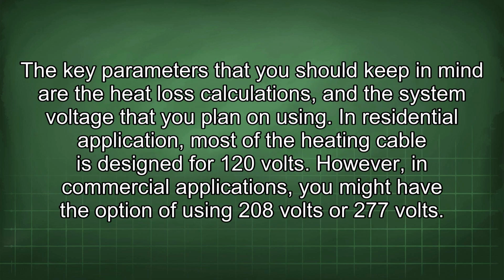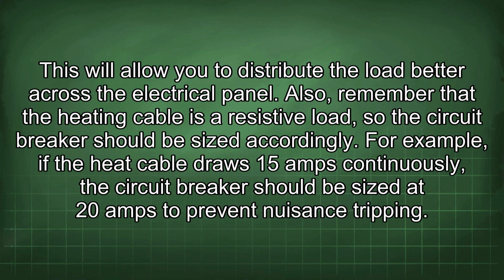The key parameters that you should keep in mind are the heat loss calculations and the system voltage that you plan on using. In residential applications, most of the heating cable is designed for 120 volts. However, in commercial applications, you might have the option of using 208 volts or 277 volts. This will allow you to distribute the load better across the electrical panel. Also, remember that the heating cable is a resistive load, so the circuit breaker should be sized accordingly. For example, if the heat cable draws 15 amps continuously, the circuit breaker should be sized at 20 amps to prevent nuisance tripping.